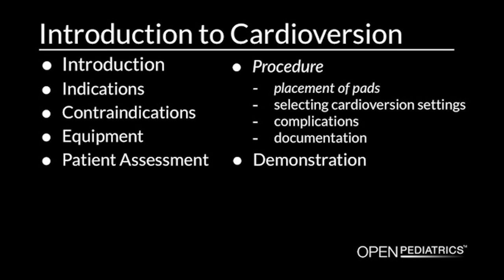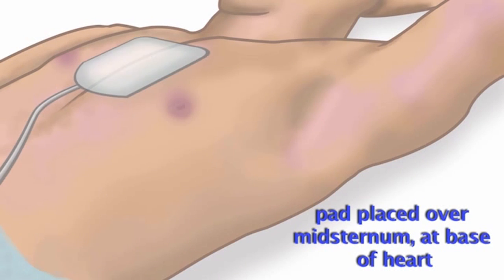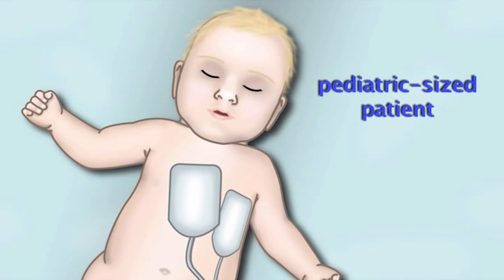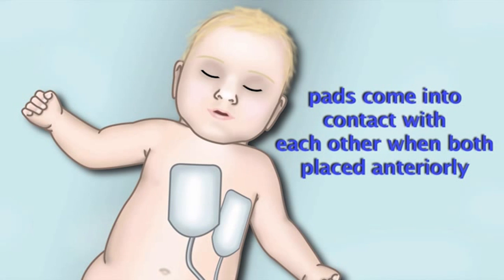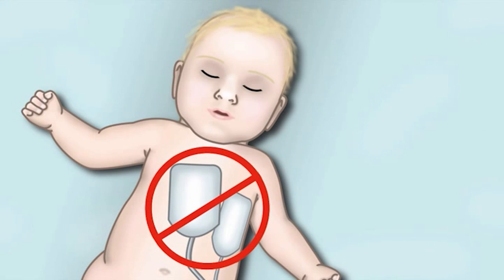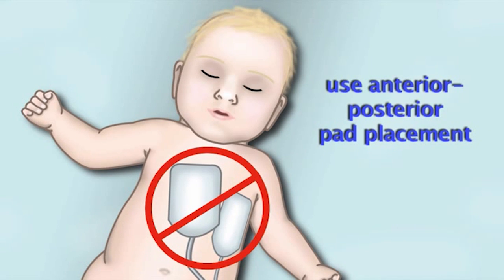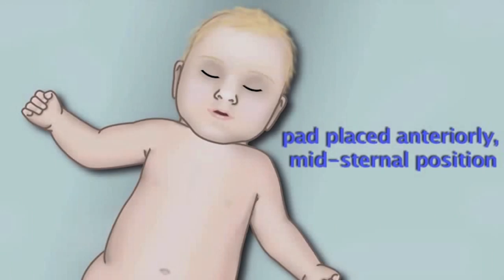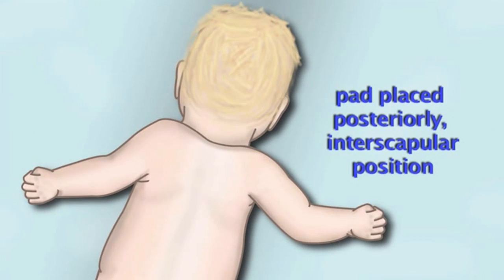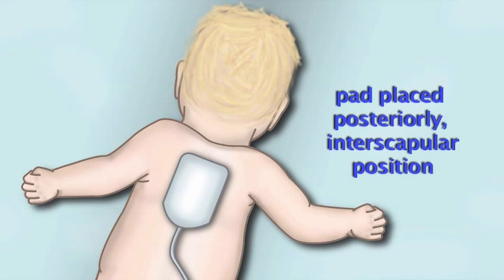For an adult-sized patient, place the pads over the mid-sternum at the base of the heart and the mid-axillary line over the apex of the heart. If you have a pediatric-sized patient and the pads come into contact with each other when placing both pads anteriorly, you should use the anterior-posterior pad placement, where one pad is placed anteriorly in the mid-sternal position and the other pad is placed posteriorly in the inter-scapular position.